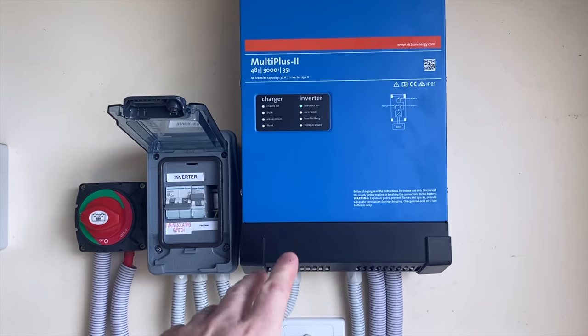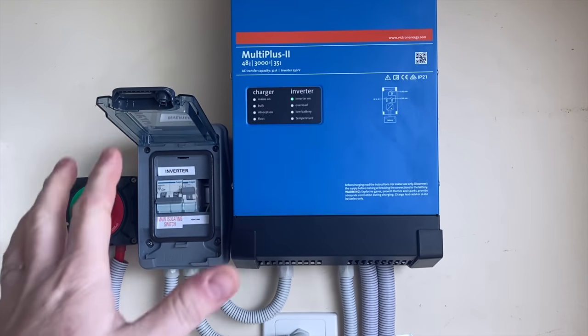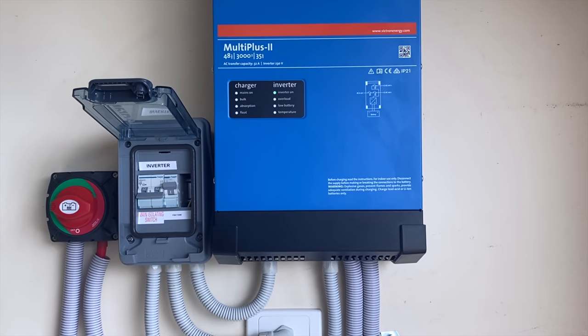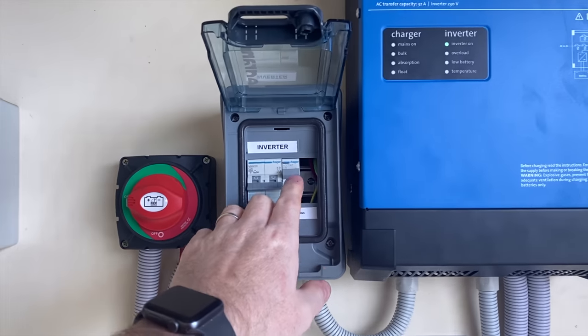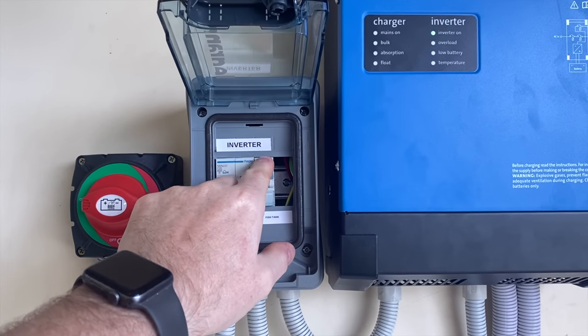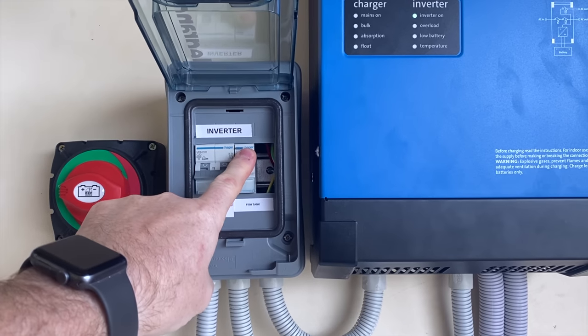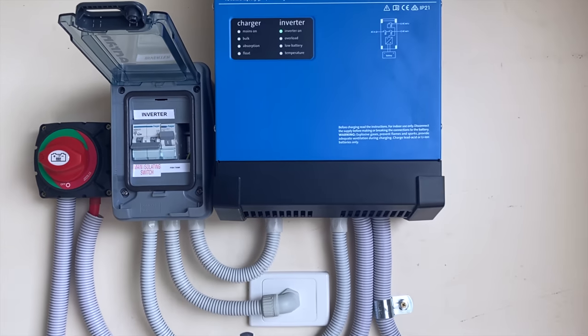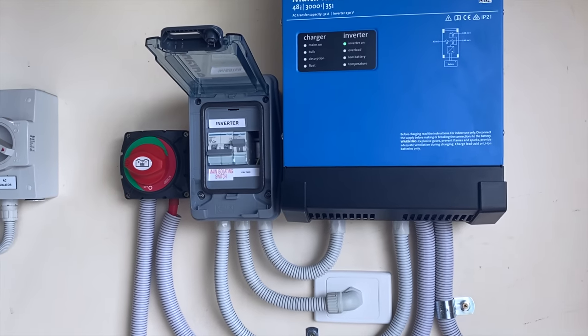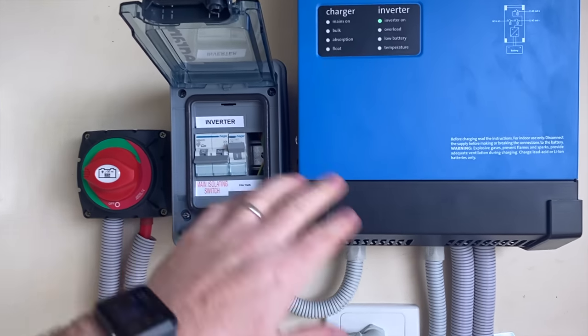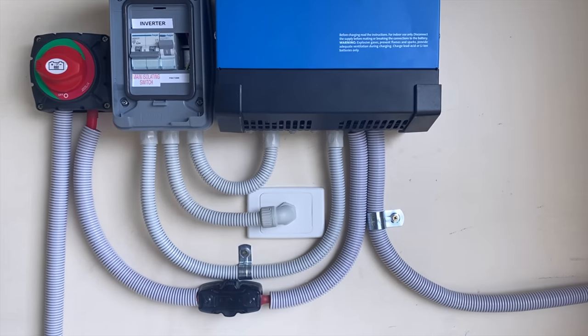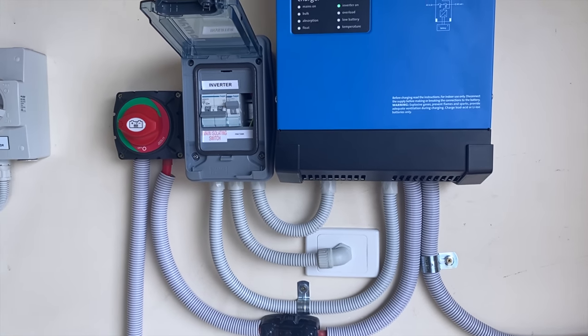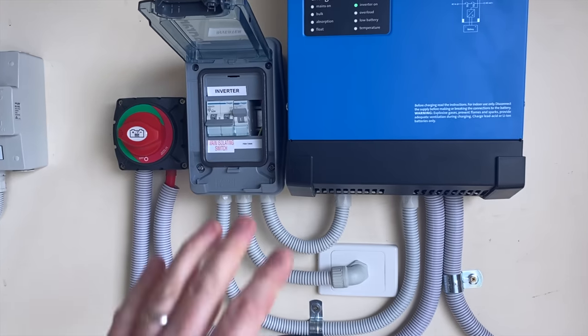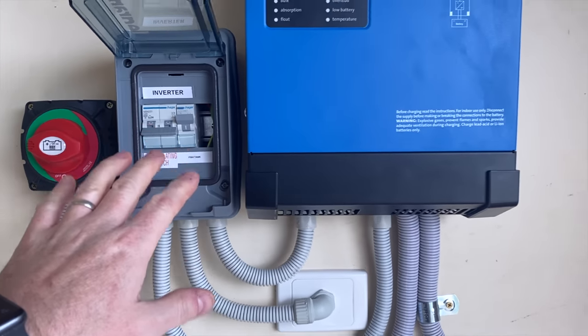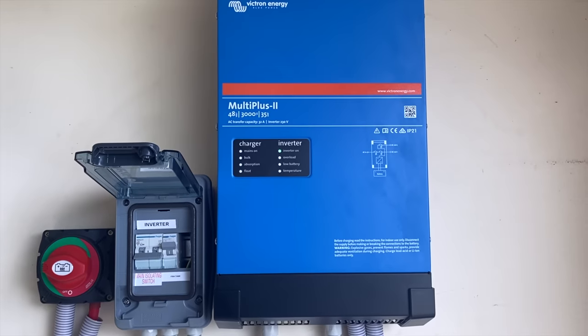To keep this system compliant, my electrician has kept the circuit breaker in the switchboard, which controls things if there's a problem with the circuit while it's powered from the grid. Then we have this other circuit breaker, which protects the system when it's running on battery but pushing AC back into that circuit. So we have to do a bit of back and forth with the wiring to keep it all completely safe and legal, but it's worth it to make sure we've got a good circuit breaker for every scenario this inverter can run from. Safety first.